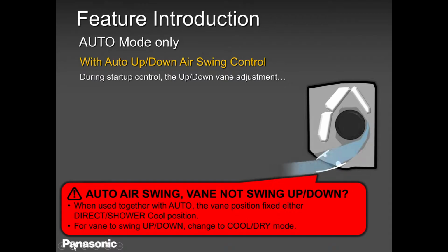You're good. Okay, sorry. So guys, again, in auto swing, in auto vane, in auto air, fan, everything is calculated. Everything is based on the temperature of the coil. If you go in our service manual, this vane goes higher or lower or downwards or middle depending on the temperature of the coil. The vane angle purely depends on the temperature of the coil, and that angle is available in our service manuals.